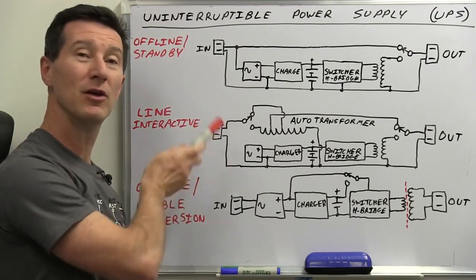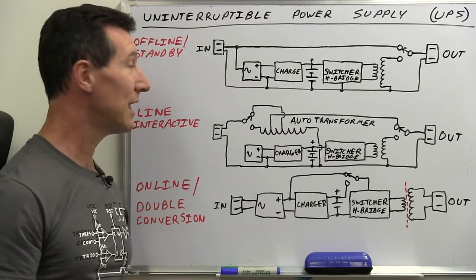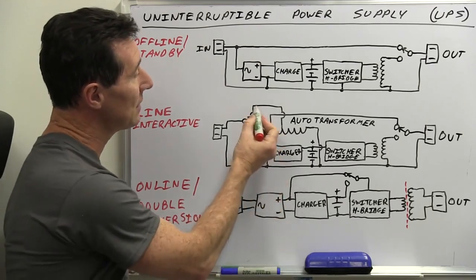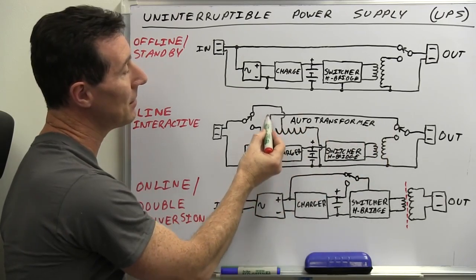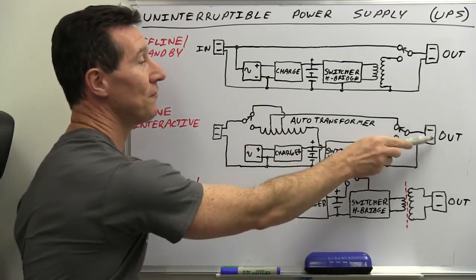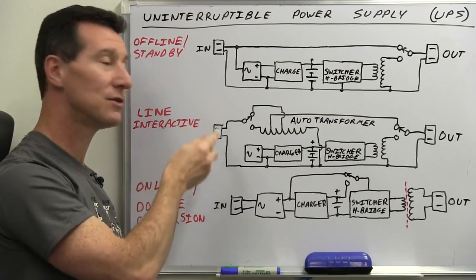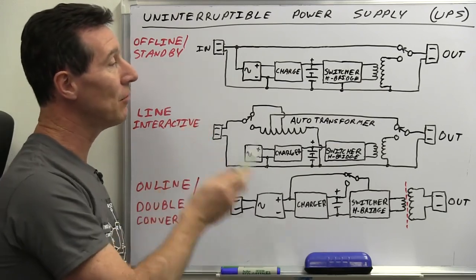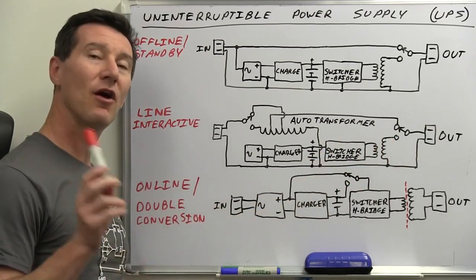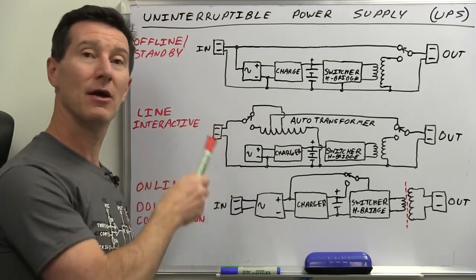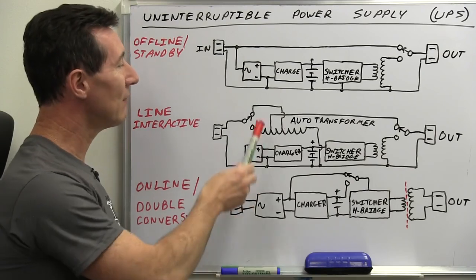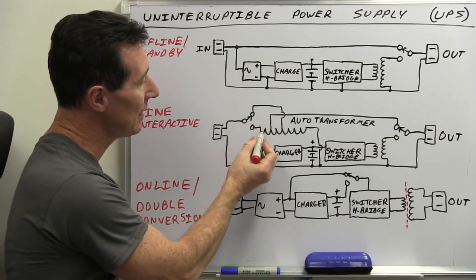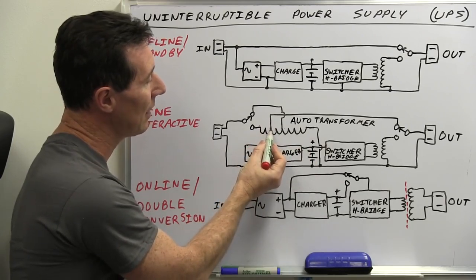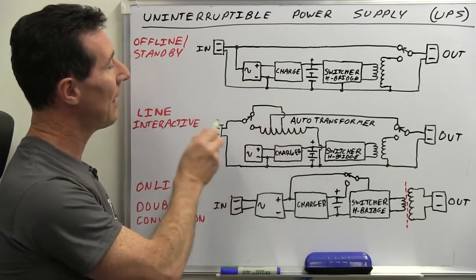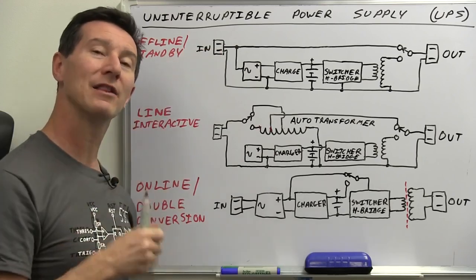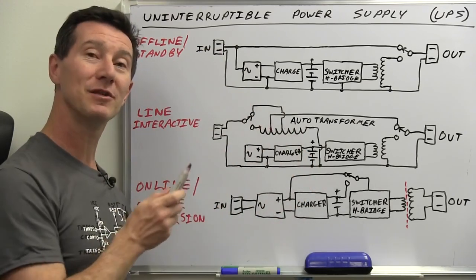So let's say your mains input is nominally 240 volts, and it drops down to 220 or 210. Then bingo, what they might do is switch to this tap here, which then means the output voltage is going to be boosted up a bit. So you're still going to get your 240 volts out. It can compensate for small variations, 10 or 20% variations in your mains input, if the device you're powering cannot handle that. And then likewise, if the mains input here goes above what your load really wouldn't like to have, then it can switch over to this tap here, and you'll notice that the output is going to be somewhere below that mains input voltage, because it's a different tap. So it can accommodate both higher and lower input voltages without having to switch over to the battery backup system.